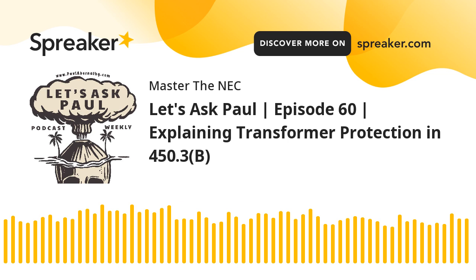In some cases, the engineer might go to 150% or 175%. Just remember that when they exceed the 125 and they're going up, that would kick in the requirement for having primary and secondary protection for that transformer.